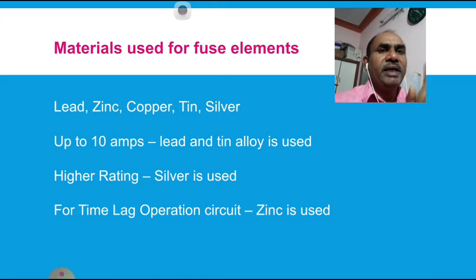And you can see at a glance the resistivity and the K value of these materials. You can see the melting point in Celsius, specific resistance and value of fuse constant K for D in mm. Silver has a melting point of 980 degrees centigrade, and specific resistance is 16, very low. Tin has a melting temperature of 240, specific resistance is 112, and the K value is 12.8. Zinc has 418 degrees centigrade, specific resistance is 60, and generally we use it for time lag purposes.